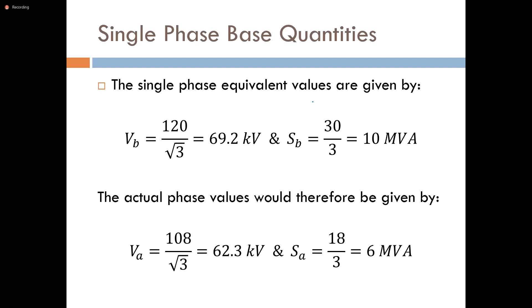So if I therefore calculate the per unit again, from the actual values, the corresponding per unit would be the actual per unit over the base per unit, which gives me back the 0.9. And the actual over the new base, which gives me back the 0.6.